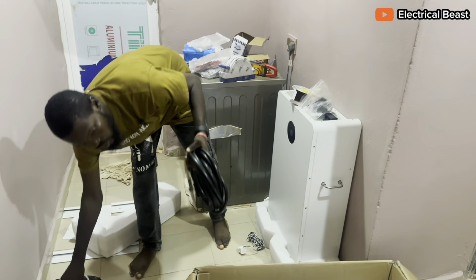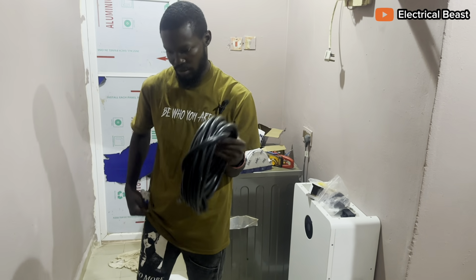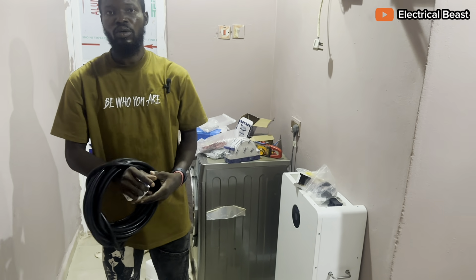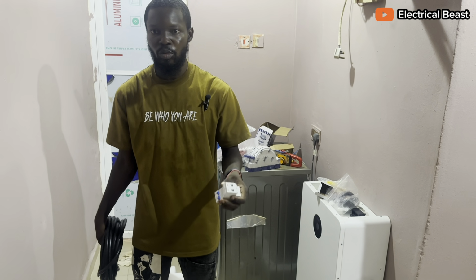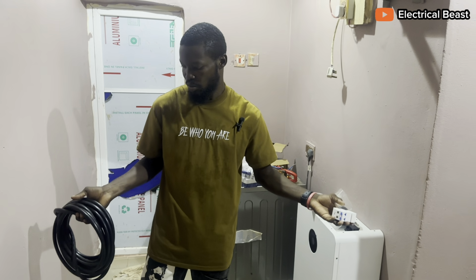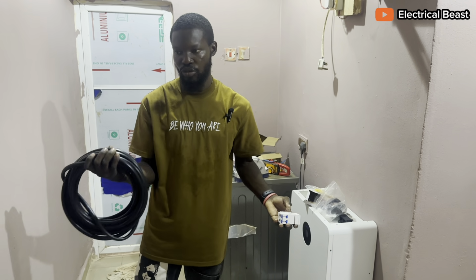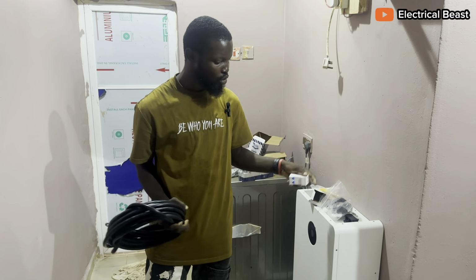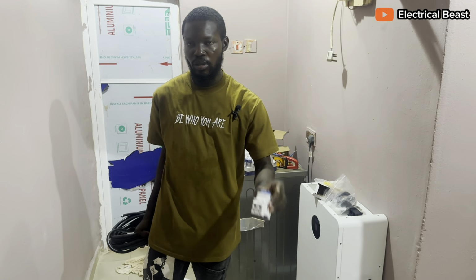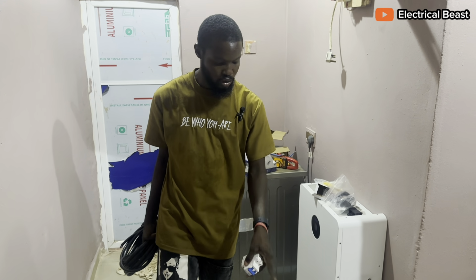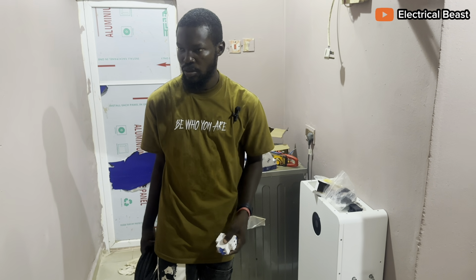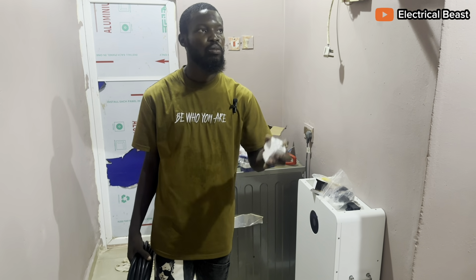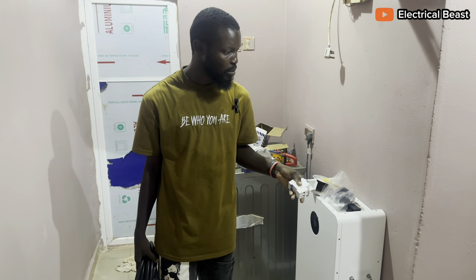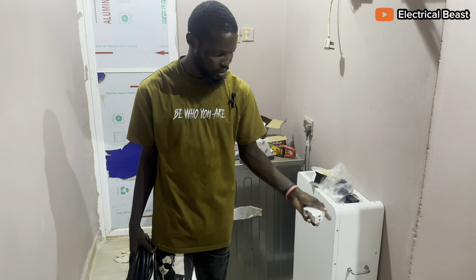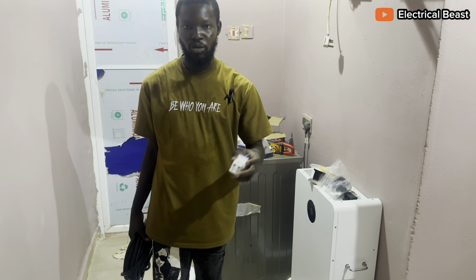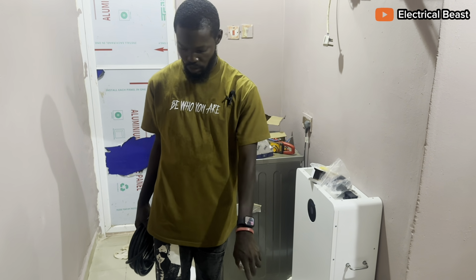Then we have 10 mm cable for the connection - it's a low current connection. You can use 6 mm cable, but it's just my personal preference to use 10 mm for connecting 9 panels in series to the inverter input. The inverter has 3 MPPT controllers inside and 6 trackers, 2 trackers per controller, but we're only going to use one for now. In time, we'll add another battery and more panels to engage the other controllers.